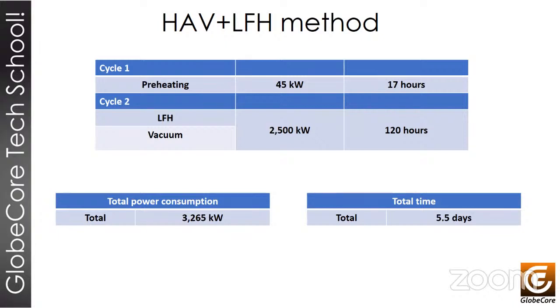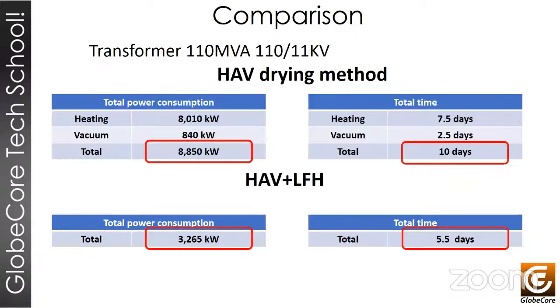Now, let's compare the data we have obtained. We clearly see the total results. In comparison, we see that the results have halved in terms of time and energy consumption. We also note that when drying the small windings, it is possible to use only one LFH system. It should be concluded that completing the package with a system of heating through low-frequency currents had a positive effect on saving the time and money associated with repair or maintenance of the transformer.